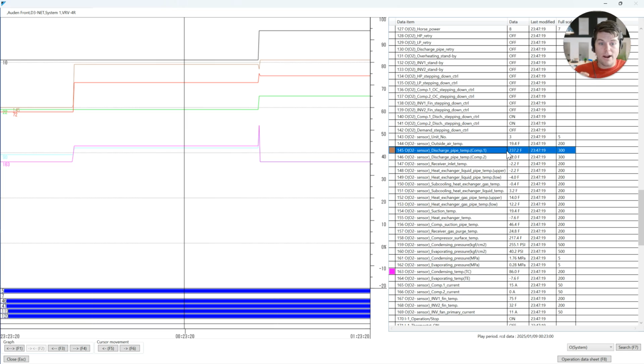And it gets to the point where if you have a 237-degree discharge temp on your compressor, the internal components are probably 275 to 300 degrees. It's usually 20 to 30 degrees higher than what you're going to see on your actual discharge temp. This means that my oil in my compressor is cooked, right? If this was a turkey on Clark Griswold's table, it would explode like in the movie.